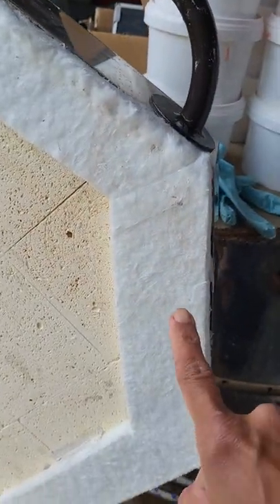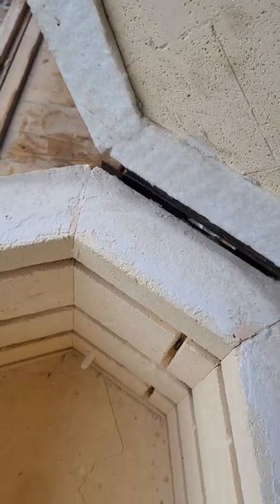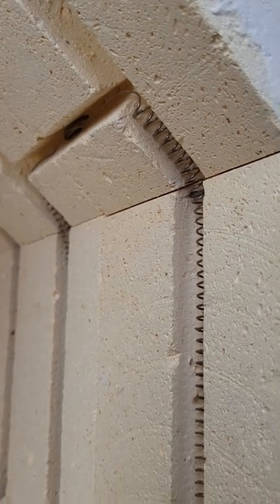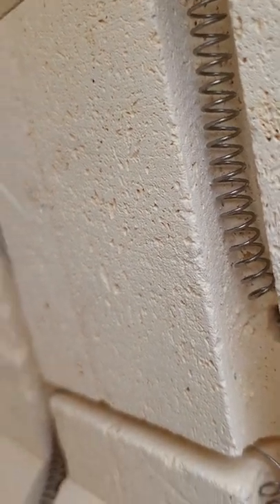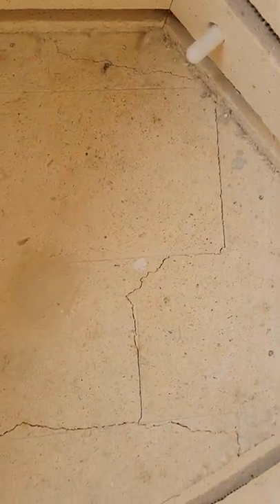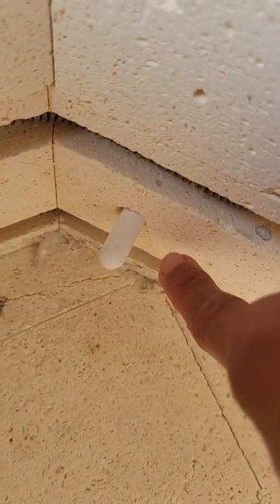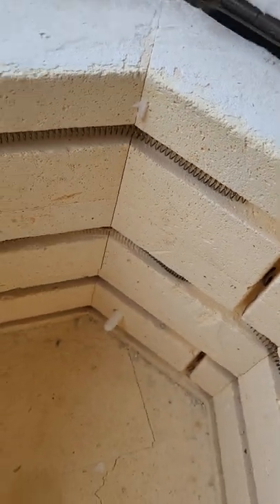There is a new gasket fitted here, and there are new elements. You need to fire this kiln empty to 1100 degrees Celsius to season its elements. Hopefully you can see the new shiny elements. As you can see, there are a few hairline cracks which do not affect the performance of the kiln — it's just superficial, and when I push it, it is not moving at all. There is the thermocouple right at the bottom of the kiln — this needs to be taken good care of, because if you knock it out it won't work, so be very careful with that.